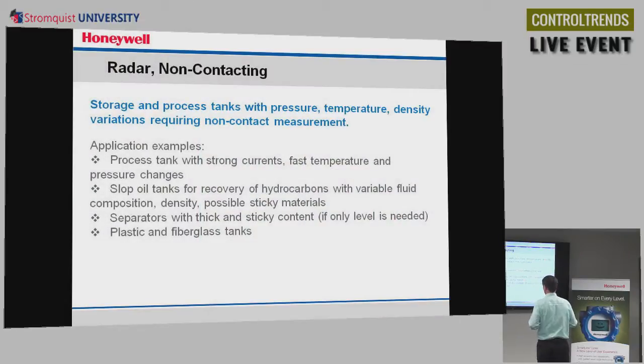Some application examples. It might be a process tank that has strong currents, fast changes in pressure and temperature. So when we're looking at a guided wave radar, we were concerned about pulling forces, forces against the side, and so forth. If there are too many forces that are pulling or acting on the waveguide, this is a good application for non-contacting. We talked about being able to measure solids too. Sometimes it's better just to use a non-contacting radar just for those concerns with pulling forces.